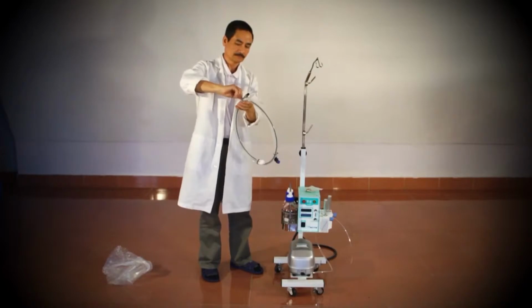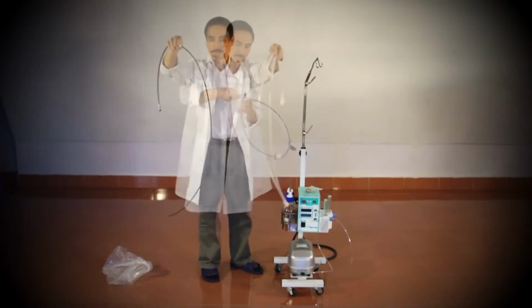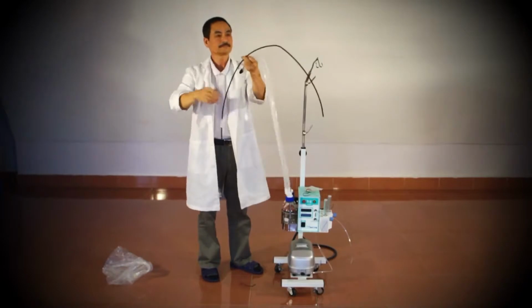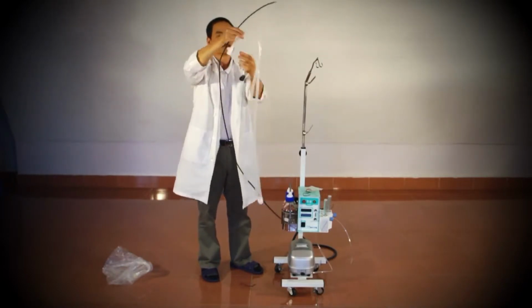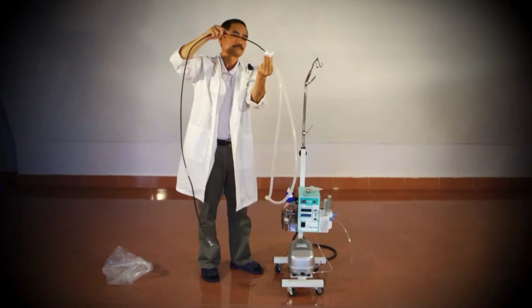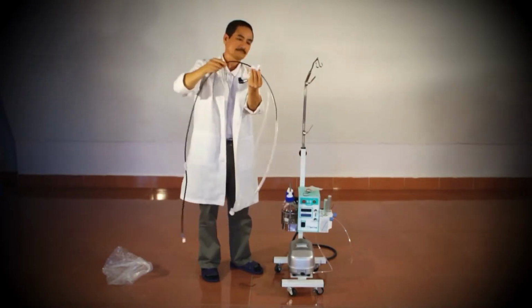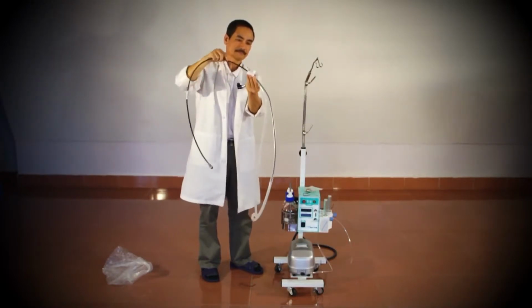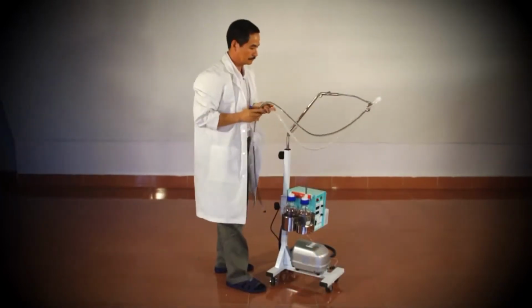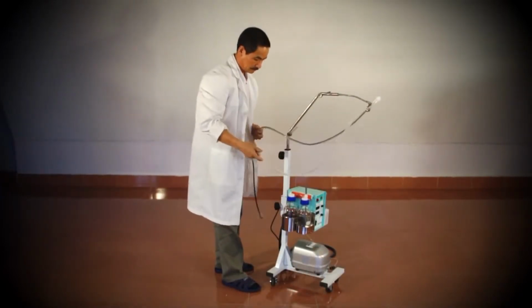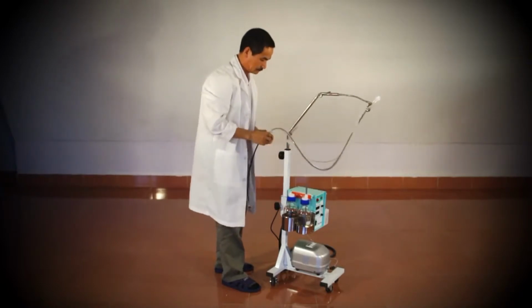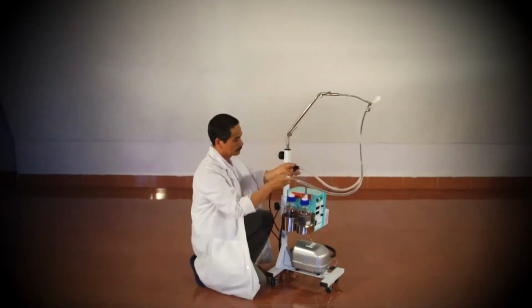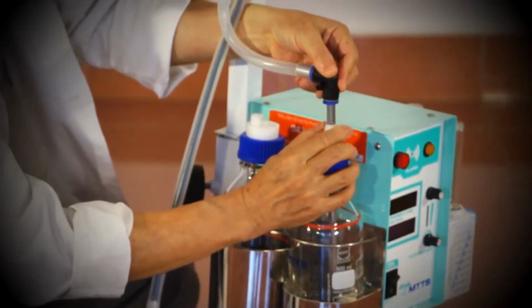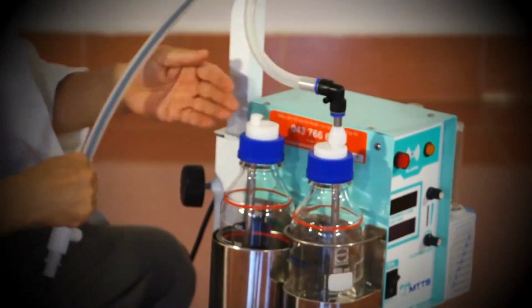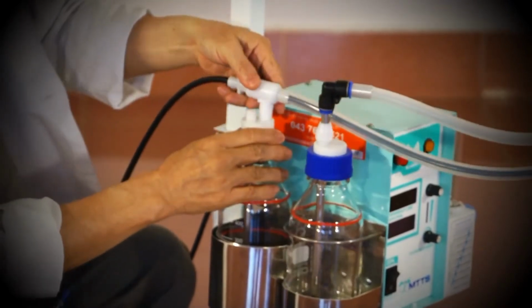Once the bottles are in place, we can connect the patient's circuit or tube set. We start by inserting the heater wire into one side of the silicone tubes, like this. Once inserted, attach the patient end of the patient circuit to the CPAP arm. Then connect each tube to its appropriate bottle. The tube is attached to the PEEP bottle. The tube with the heater wire is attached to the humidifier bottle.